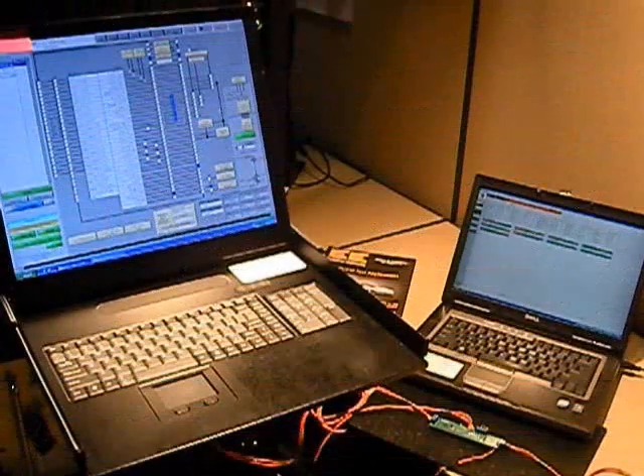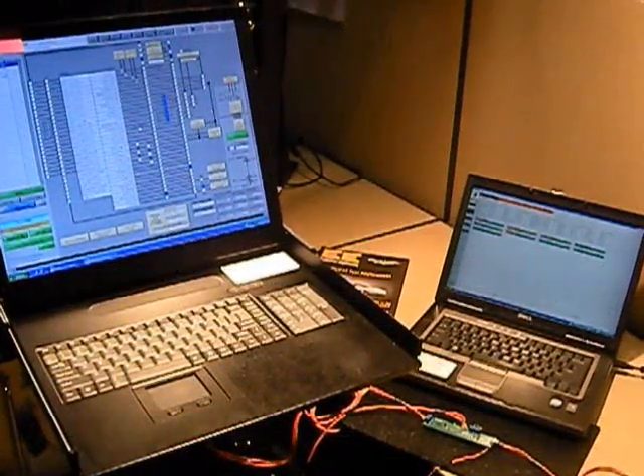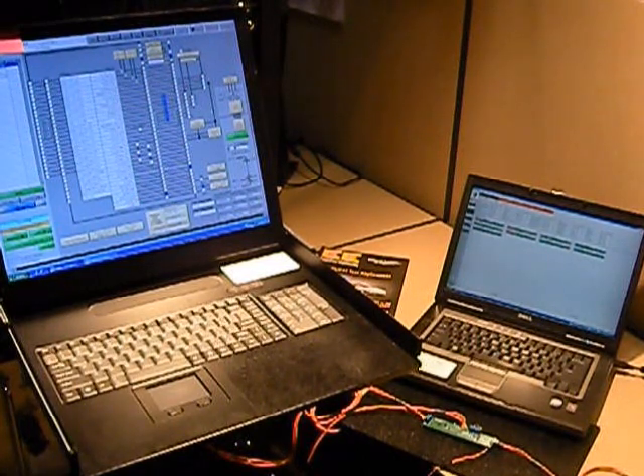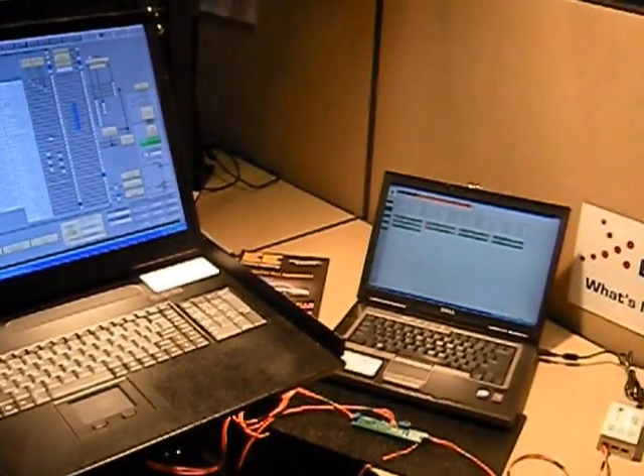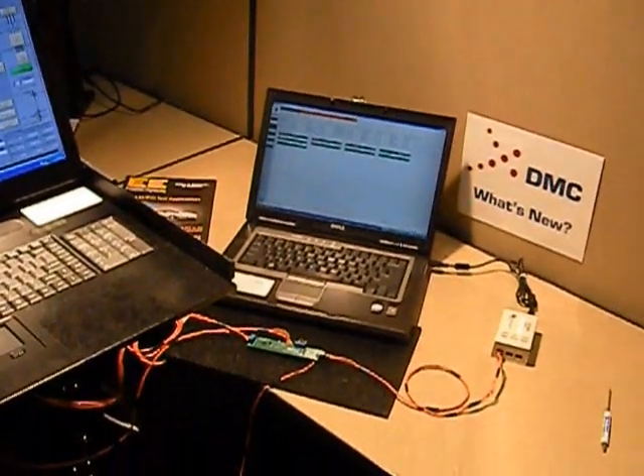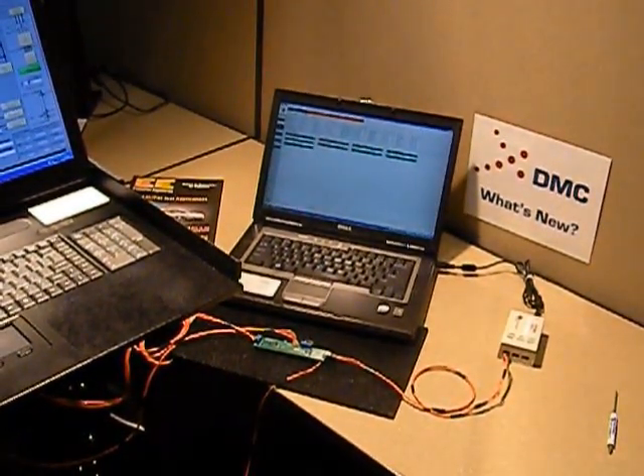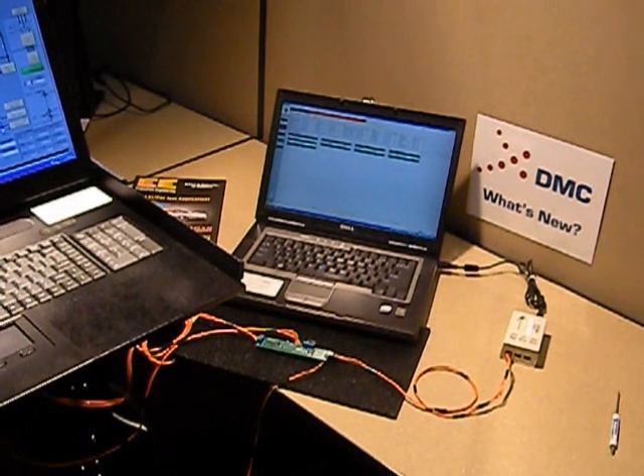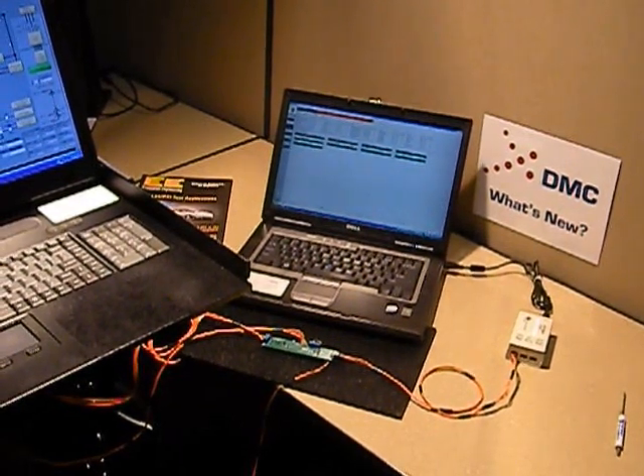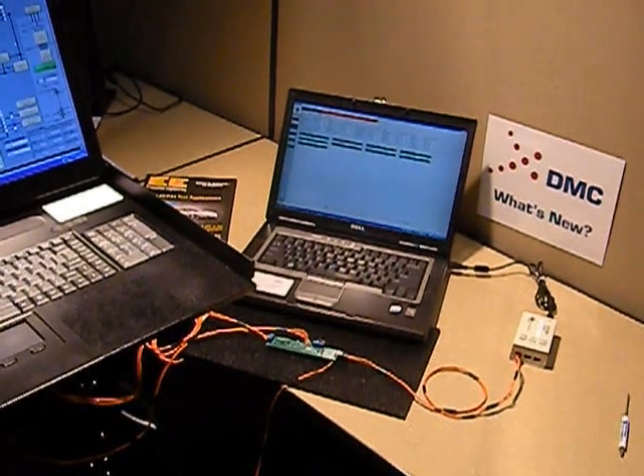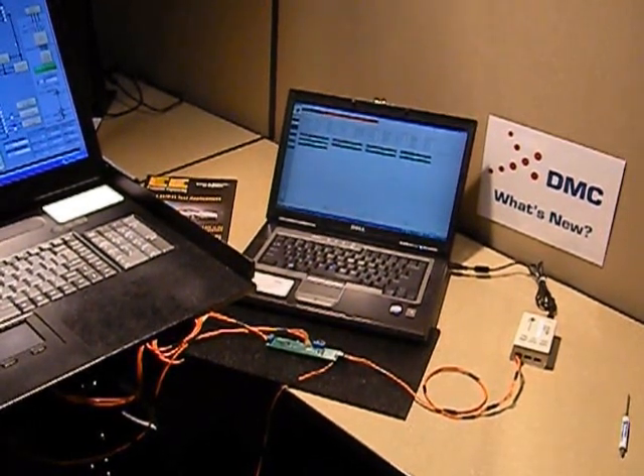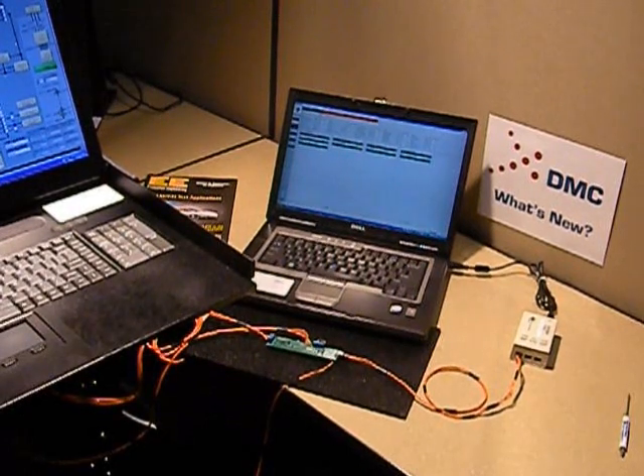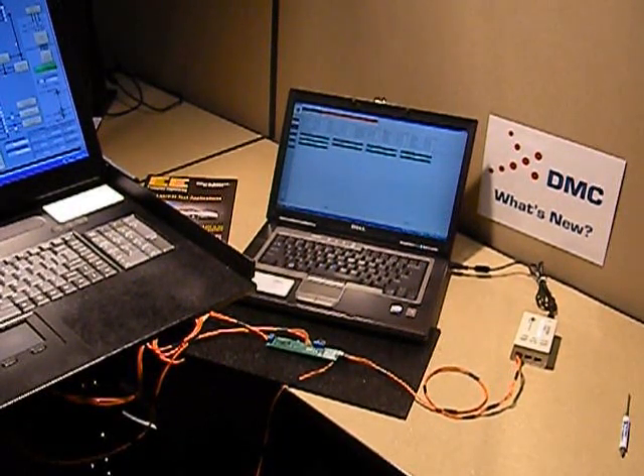And you can see that it's a very complex waveform due to the BMS powering itself off of the cell stack. Today we've demonstrated for you the BMS test stand developed and produced by DMC. We've used a Texas Instruments 4-cell BMS system as a demonstration of a typical BMS that we would test with this system. We've used their evaluation module software and an SMBUS to USB converter all by Texas Instruments to demonstrate the outputs from this BMS.